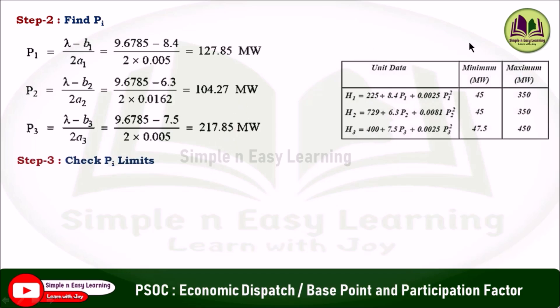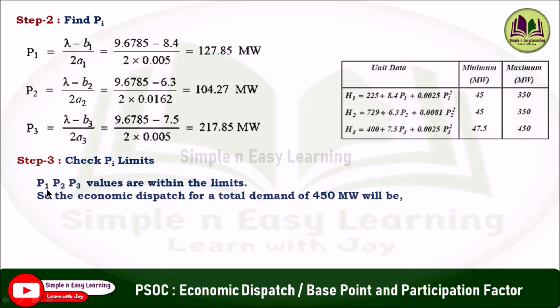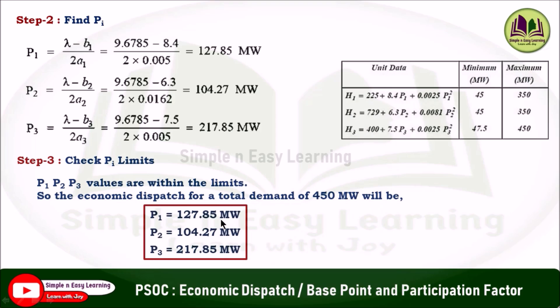Now check the limits. The minimum and maximum limits for each unit are given. For unit 1, the minimum is 45 and maximum is 350 — P1 = 127.85 MW lies within the limit. Unit 2 (45 to 350) and unit 3 with P3 = 217.85 MW also lie within limits. Therefore, the economic dispatch for 450 MW is: P1 = 127.85 MW, P2 = 104.27 MW, P3 = 217.85 MW.